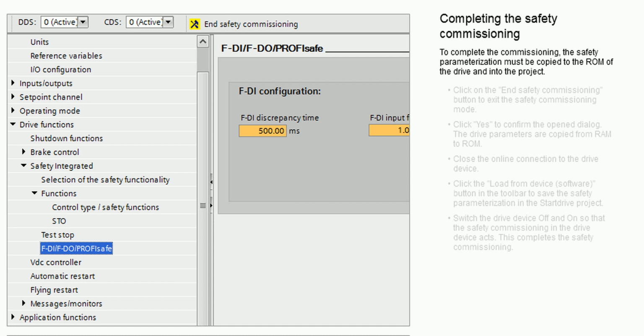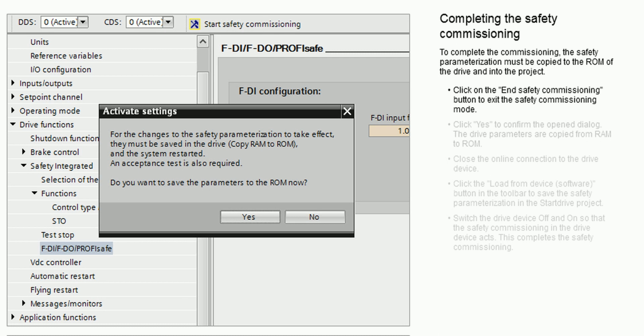To complete the commissioning, the safety parameterization must be copied to the ROM of the drive and into the project. Click on the End Safety Commissioning button to exit the safety commissioning mode. Click Yes to confirm the open dialog. The drive parameters are copied from RAM to ROM.